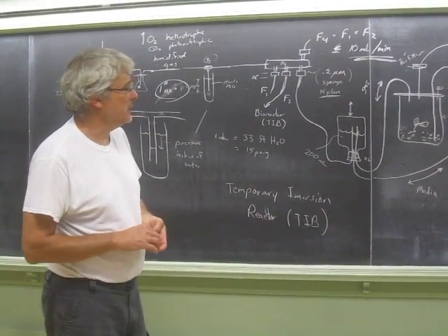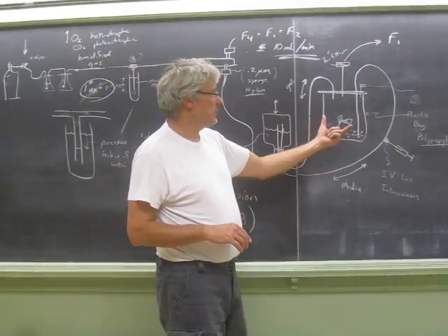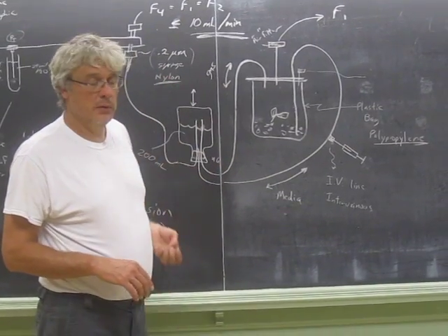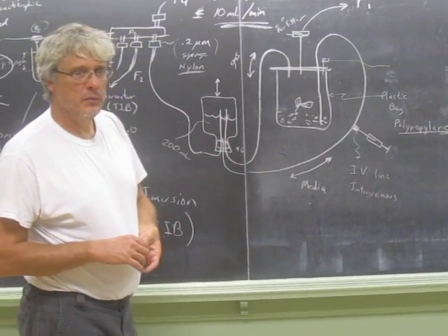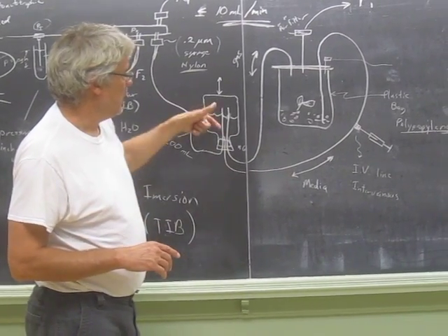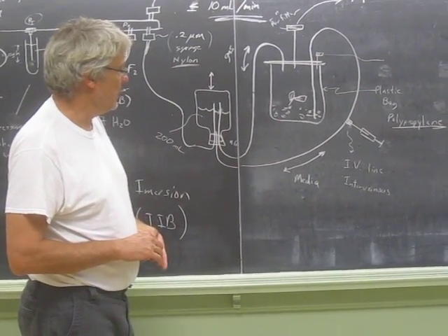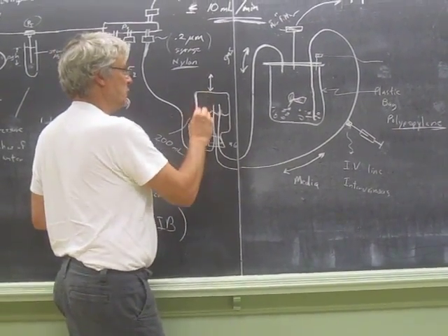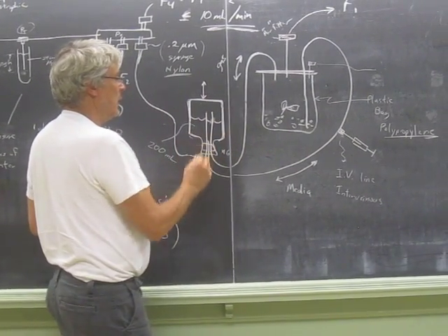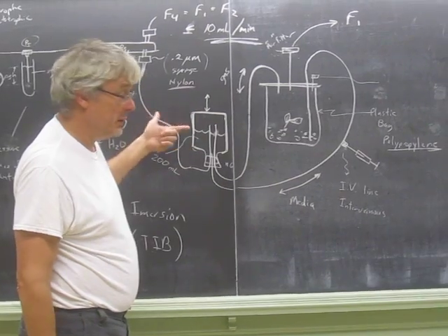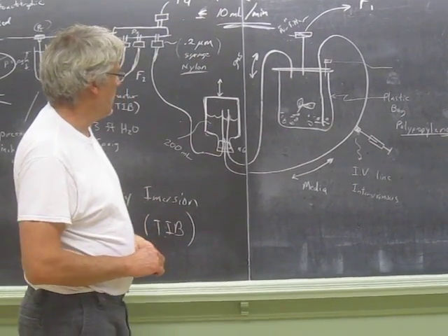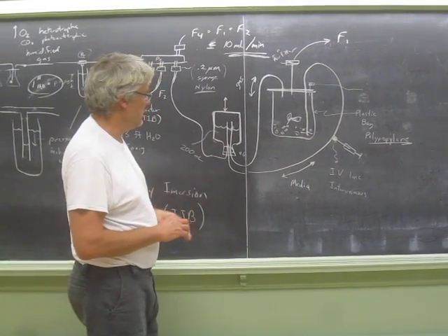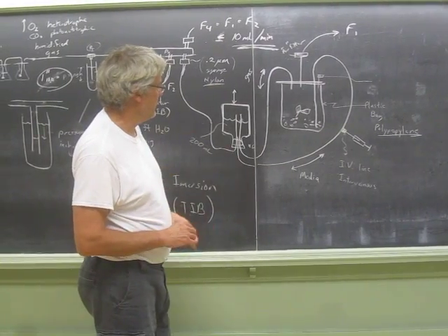I do have one more comment, and that is it's possible that you could actually raise and lower the reactor instead of raising and lowering the reservoir. And we had worked a little bit with that before, and we found it much easier to deal with the raising and lowering of the reservoir itself. The stepper motor has to be sized to handle the weight. We have actually used, for instance, plastic bottles before, because they're less weight and therefore the stepper motor can be simpler. But the advantage of using glass, of course, is that it's crystal clear and you can actually see inside to see if you have any problem with contamination.